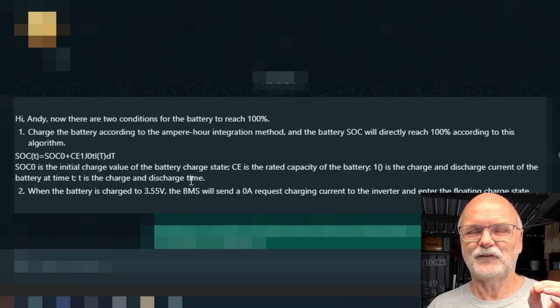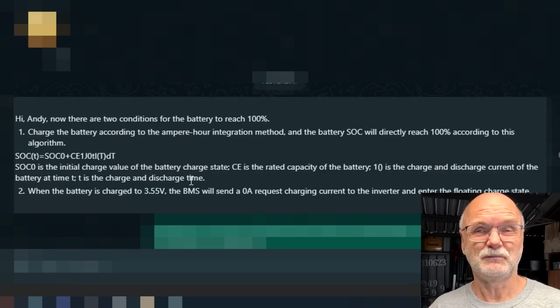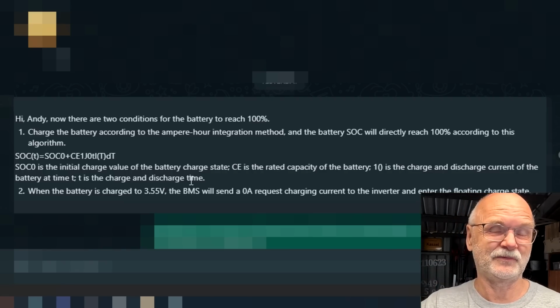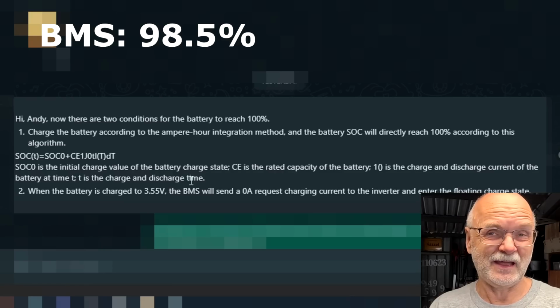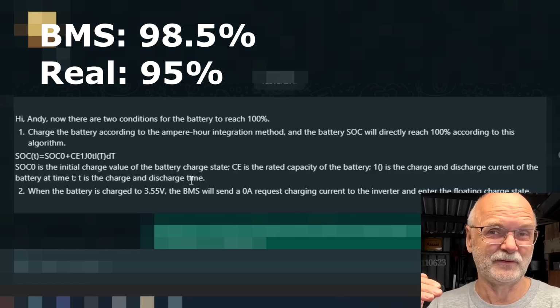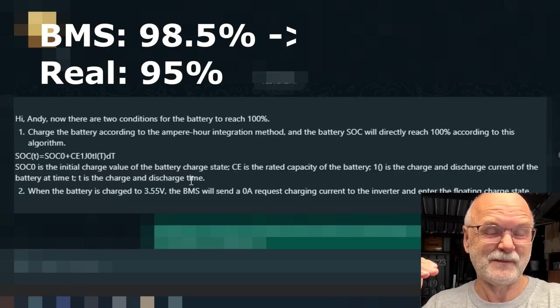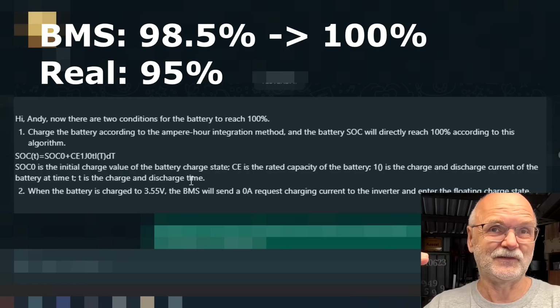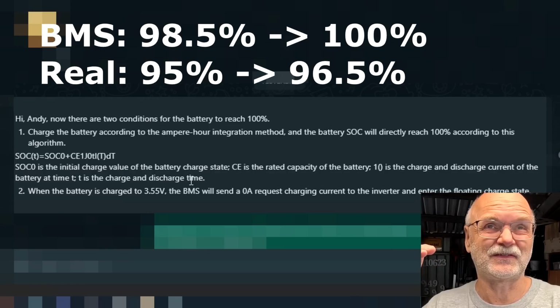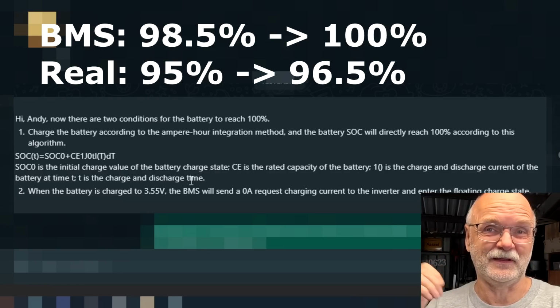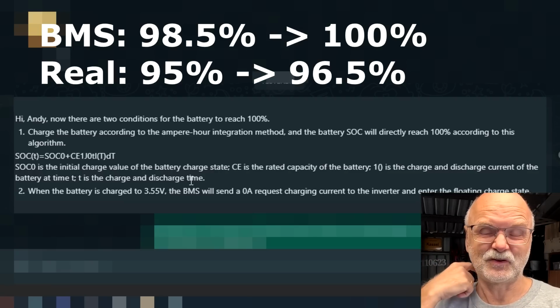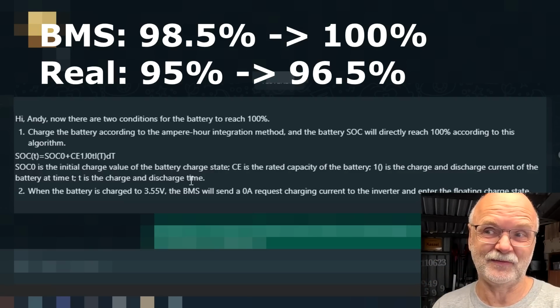There's a bit of a concern here that you actually hit 100% state of charge before the battery is really at 100%. Because if the BMS shows 98.5% but your battery is only at 95%, you keep charging, and your BMS shows 100% but your battery is only at 96.5%. So it's not really at 100%, but you can only see this by looking at the voltage, not the percentage.